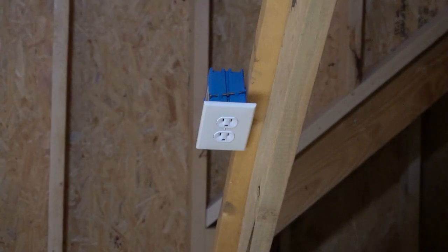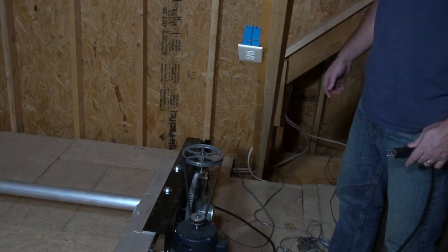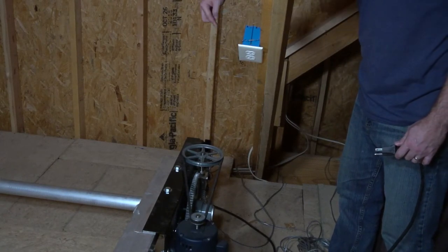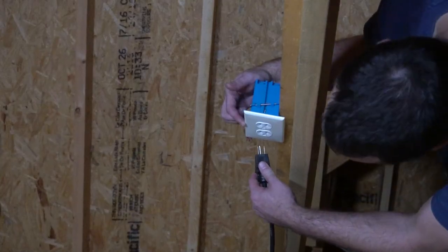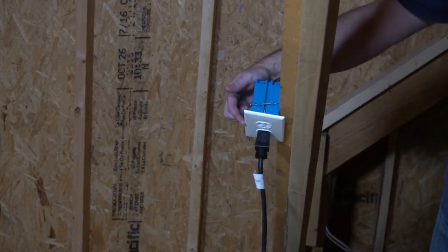Install a dedicated 110 volt circuit receptacle to supply power to the motor drive assembly. Receptacle should be within three feet of the motor drive assembly service switch box. Plug in the three feet pigtail pre-wired to the service switch from the factory.